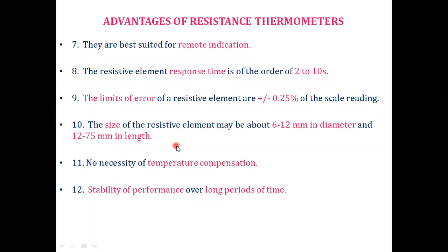The size of the resistive element may be of about 6 to 12 mm in diameter and 12 to 75 mm in length. The diameter is 6 to 12 mm and the length is 12 to 75 mm. No necessity of temperature compensation.